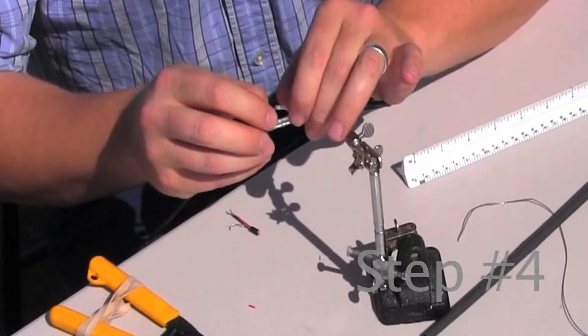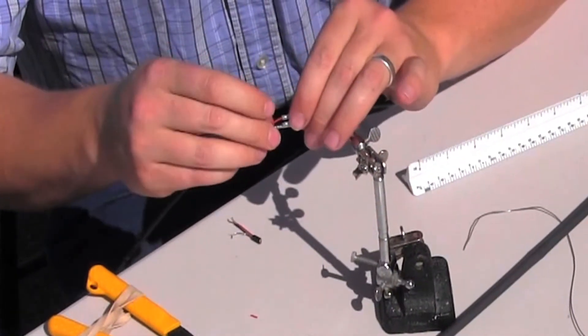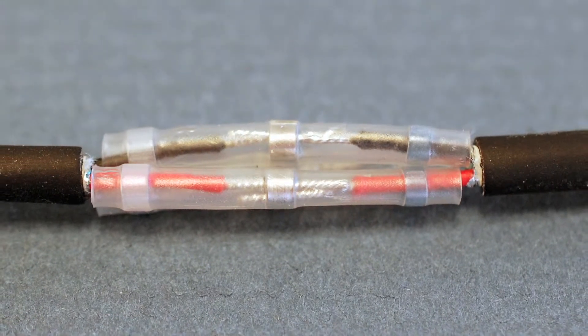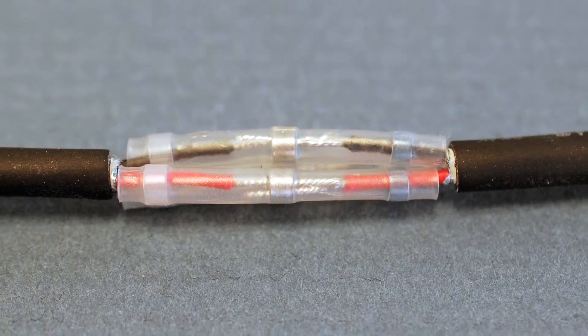Step four: slide the cable that is to be spliced into the other end of the solder sleeve, making sure the tinned ends are inside the solder rings. Verify that the wires match up, for example, red to red, black to black, and so on.